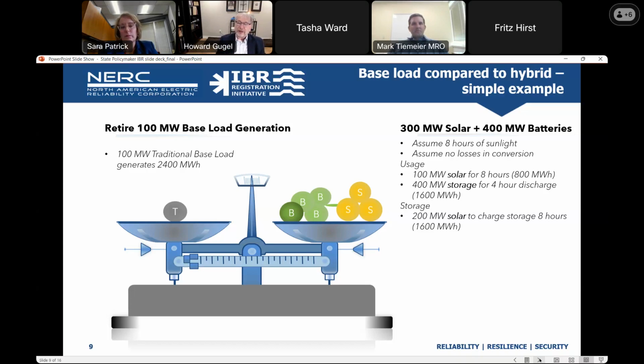So what does that mean? I've got to charge those batteries during the time when the sun is shining, so I need 200 megawatts of solar to charge those batteries during the 8 hours. So if I want to do a 1-for-1 replacement of 100 megawatts that was baseload running around the clock, with a combination of solar and batteries, using the assumptions here, I need 300 megawatts of solar and 400 megawatts of batteries installed to replace that 100 megawatts. Is that good? Is it bad? No, it's just a reality. That's how you do the trade-off there.